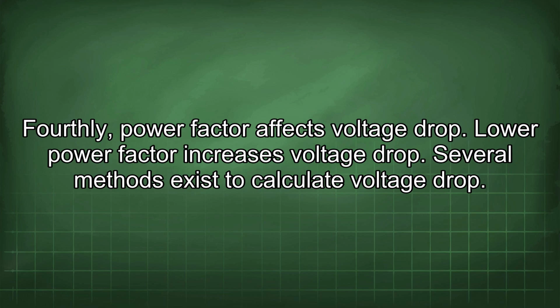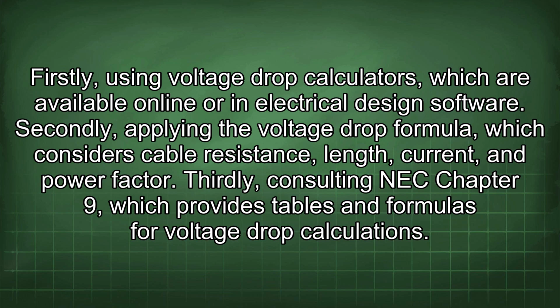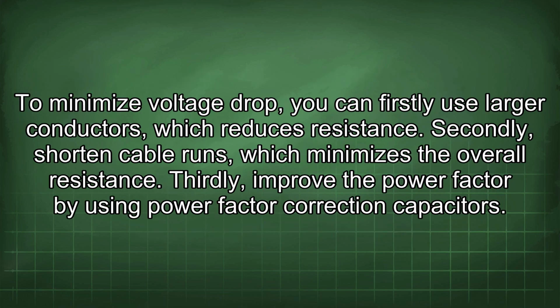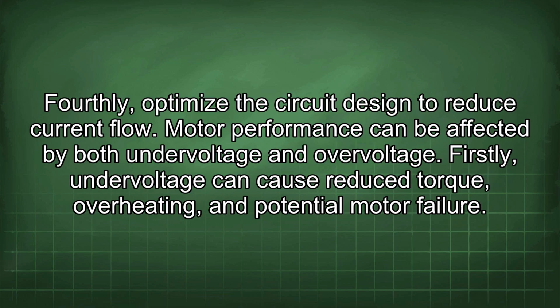Several methods exist to calculate voltage drop. Firstly, using voltage drop calculators, which are available online or in electrical design software. Secondly, applying the voltage drop formula, which considers cable resistance, length, current, and power factor. Thirdly, consulting NEC Chapter 9, which provides tables and formulas for voltage drop calculations. To minimize voltage drop, you can firstly use larger conductors, which reduces resistance. Secondly, shorten cable runs, which minimizes the overall resistance. Thirdly, improve the power factor by using power factor correction capacitors. Fourthly, optimize the circuit design to reduce current flow.